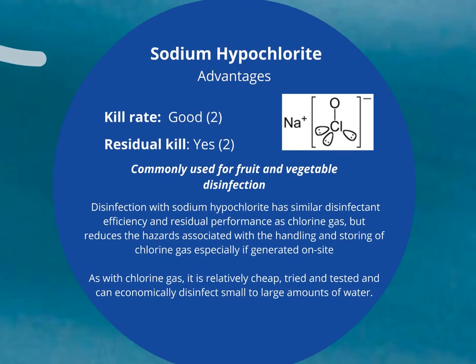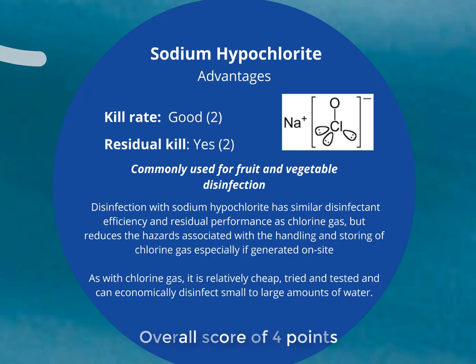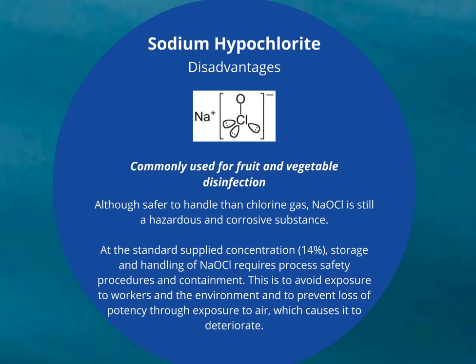The first disinfectant is sodium hypochlorite. The kill rate is good, so we've given it a two, and it also has residual kill, so that's another two points. Disinfection with sodium hypochlorite has similar disinfectant efficiency and residual performance as chlorine gas, but it reduces the hazards associated with handling and storing chlorine gas, especially if it's generated on site. As with chlorine gas, it's relatively cheap, tried and tested, and can economically disinfect small to large amounts of water. Although it's safer to handle than chlorine gas, it still does have a hazardous and corrosive element.